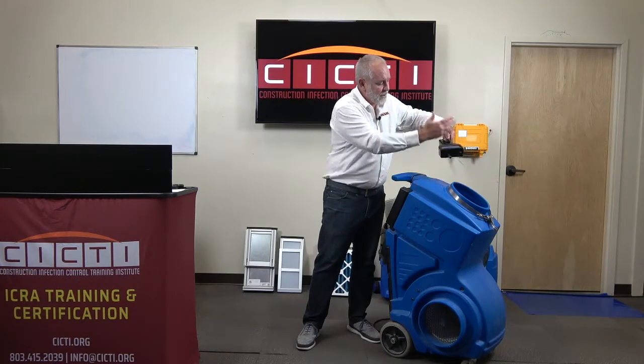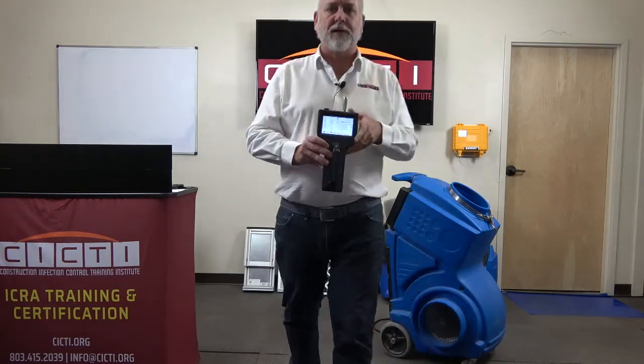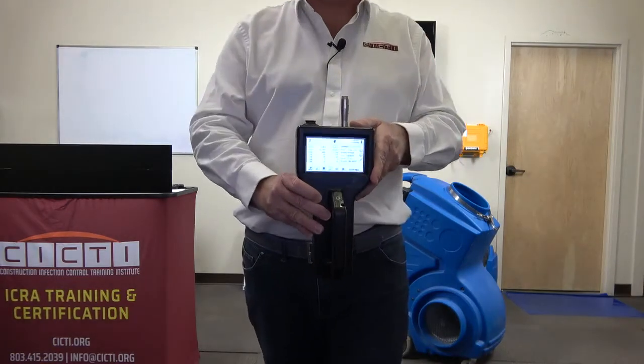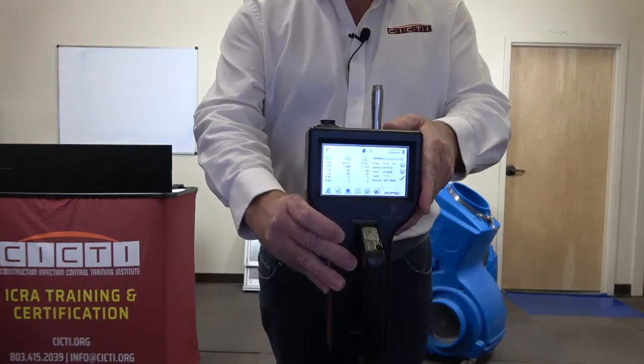If I were to hold the device vertically, I'd be jamming the air into the probe. And if I held it upside down with the probe pointed at the device, I'd be shadowing or shrouding the free airflow into the inlet, and that might not lead to the most accurate sample. So typically when we test air-flowing systems, it's perpendicular to the direction of airflow.